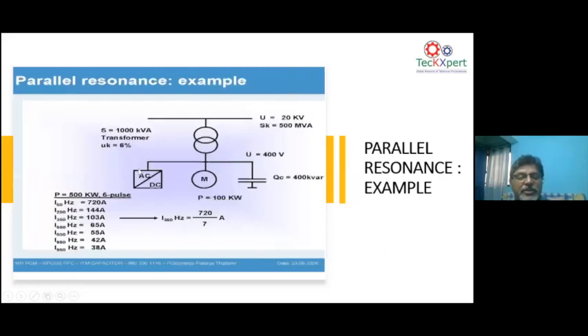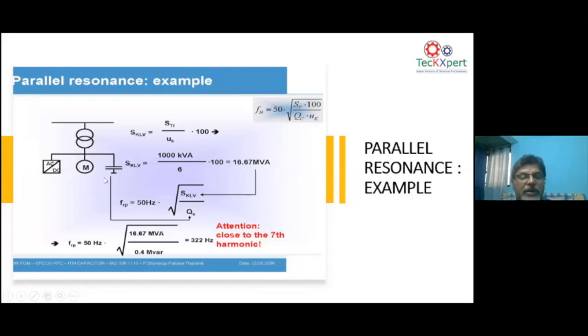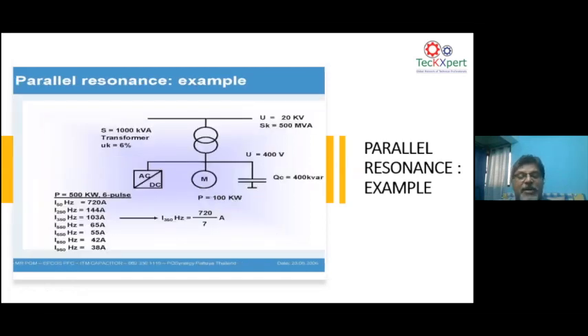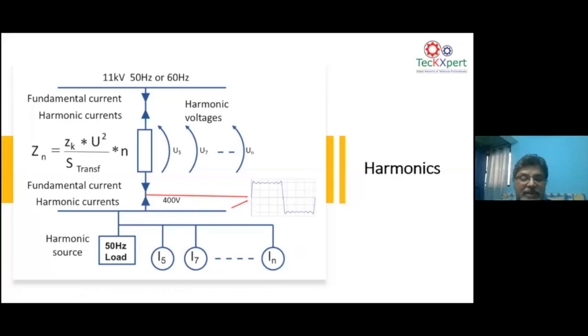The natural frequency of the network is calculated from the short circuit level in MVA divided by the MVAR. So for a 1000 kVA transformer, 16.6 divided by the percentage impedance gives you the short circuit capacity. And you divide the short circuit capacity by the 0.4 MVAR. It's all an MVA and MVAR relationship. So you get 322 as the natural frequency of this network. Now assume you have a variable frequency drive producing fifth harmonic and seventh harmonic. What happens? The seventh harmonic will naturally get amplified. That is what it is showing here.